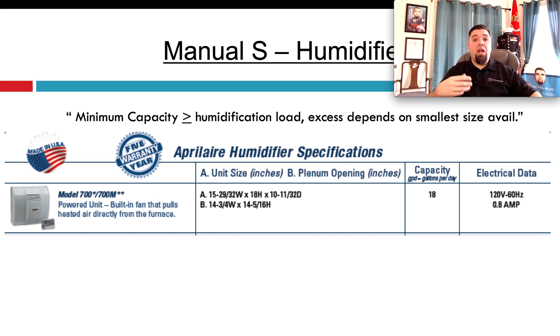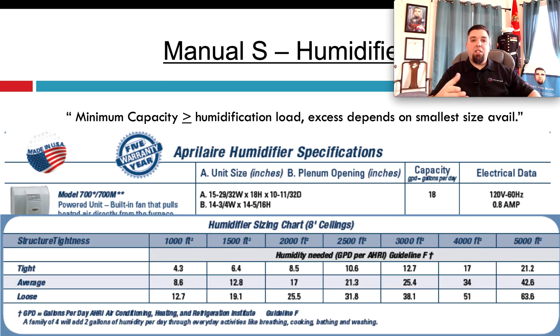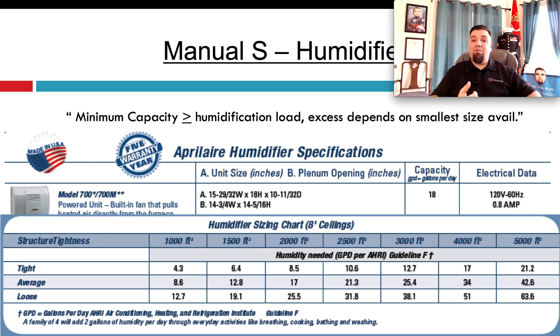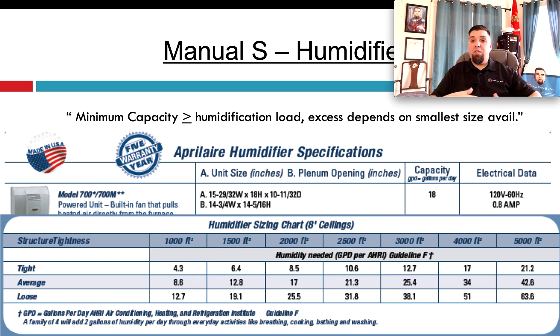The humidity requirement is also based on the number of people in the home and the size of the home. As an example, this is Aprilaire's humidifier sizing chart based on square footage and the tightness of the house. In this example, let's say we have a 2,500 square foot home and it's rated as average tightness — that's what we set it for in our load calculation.